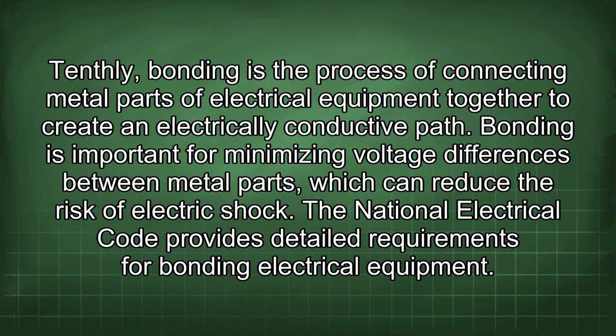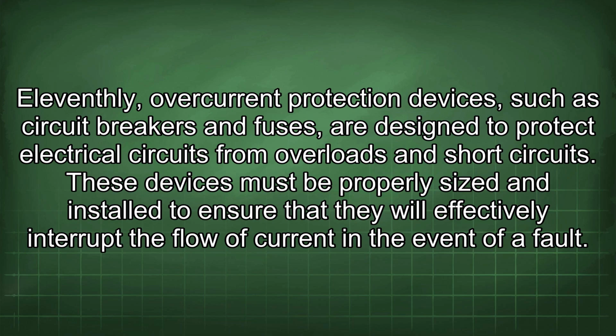Tenthly, bonding is the process of connecting metal parts of electrical equipment together to create an electrically conductive path. Bonding is important for minimizing voltage differences between metal parts, which can reduce the risk of electric shock. The National Electrical Code provides detailed requirements for bonding electrical equipment. Eleventhly, overcurrent protection devices, such as circuit breakers and fuses, are designed to protect electrical circuits from overload and short circuits.